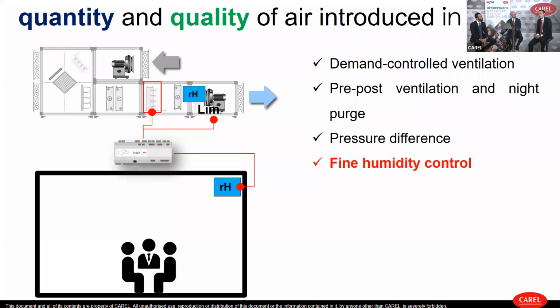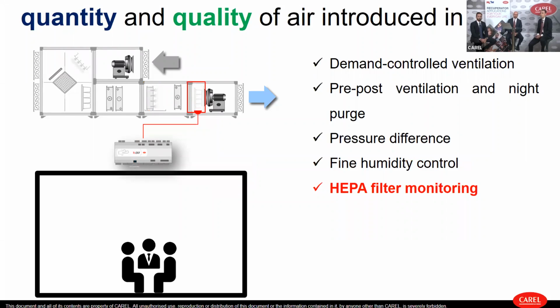But it's important not only to control properly the humidifier, but also to control that the humidifier does not become a source of proliferation of bacteria or contamination, by avoiding condensation inside the humidification chamber. So having a control on the supply air with the limit probe can adjust this level in order to prevent this particular risk. Another interesting feature is the control of the filtration.